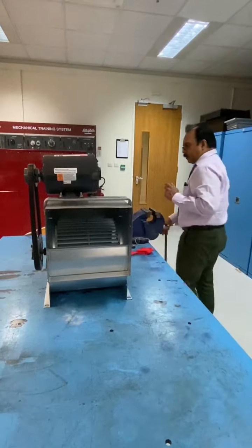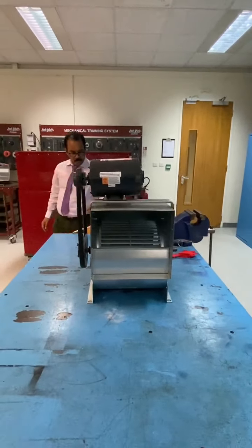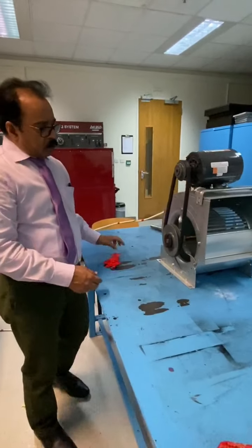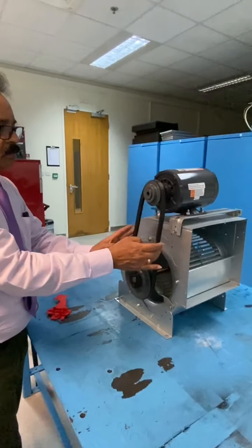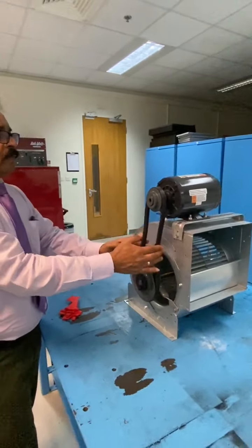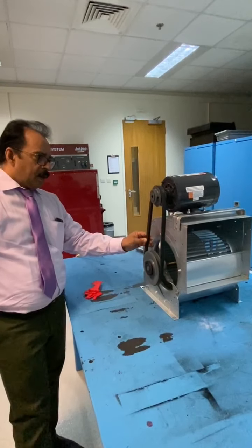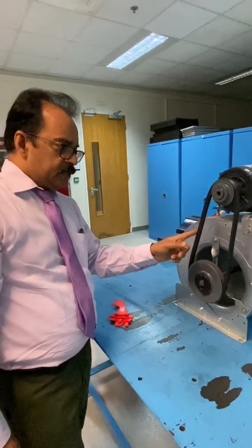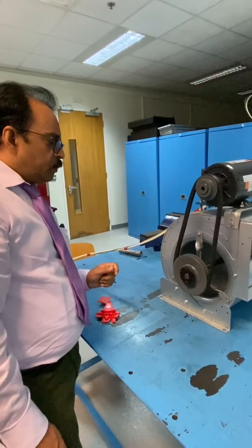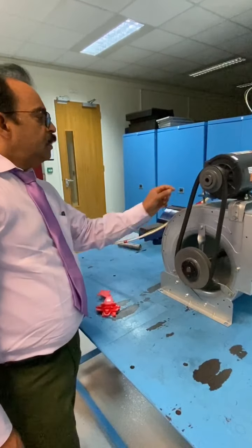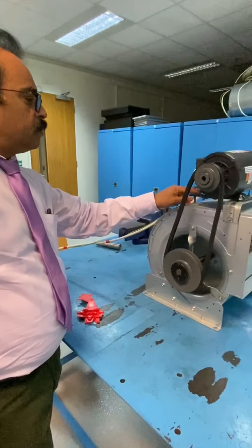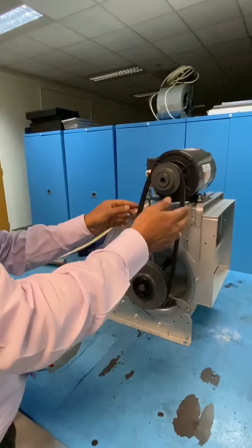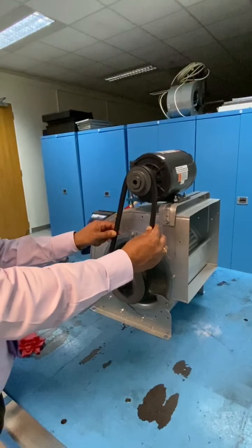And then the next one is the tensioning of the belt. Look at here, this belt is very loose. So that means this is not tightened properly. After explaining, when we start, you will see that the belt is not tensioned. So you need to do tensioning. For tensioning, you need to remove this bolt and everything and push and also raise it a little up so that the belt will get the proper tension.